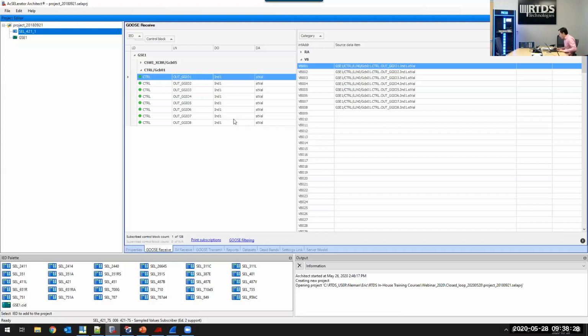Firstly, the GTNet Goose configuration is imported into the Architect using the SCD file that's saved from the SCD Editor. Then the GTNet outputs, the GTNet output data set, are mapped to the relay's Goose inputs. So these are the GTNet outputs, and these are the relay's Goose inputs. The next step is a Goose data set.